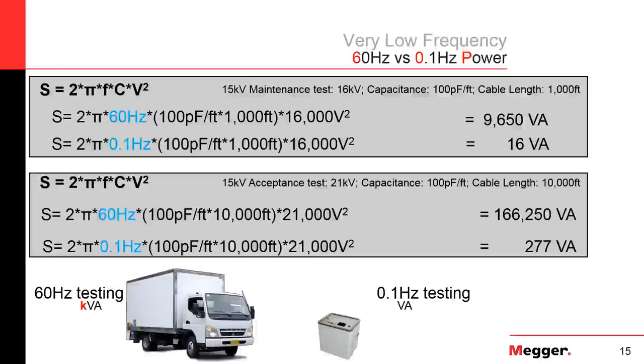If we take this 15 kV class cable, do a maintenance test on it, cable's 1,000 feet long, would need just under 10,000 watts of power just to charge a cable up if we do it at 60 hertz. But if we do the test at VLF frequency, it takes less than 20 watts. So maybe I can go down to the local hardware store and buy a 10 kilowatt generator, but it's probably the biggest one they have on site. And that doesn't take into account any losses or anything. And again, this is only a 1,000 foot cable.